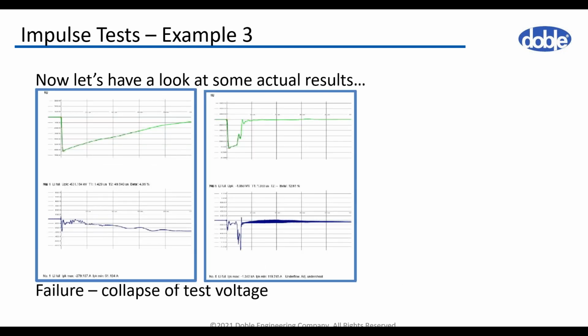Here again is an example from the real test field. On the left rectangle, you can see voltage on top and current oscillograms at reduced test voltage. And on the right side of your screen, the subsequent voltage and current oscillograms at 100% test voltage. You can see on the right side there is significant difference in both current and voltages compared with the reference value, and this is because a failure occurred. So this is how an oscillogram indicating a problem would look like.